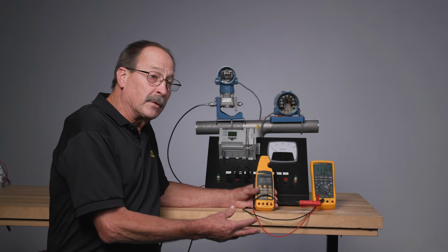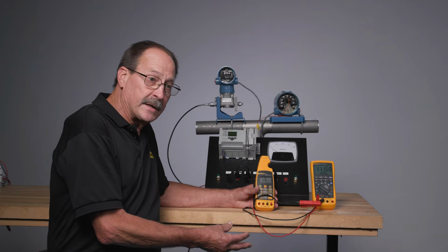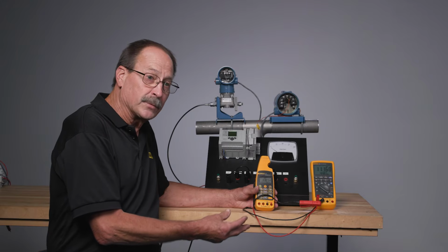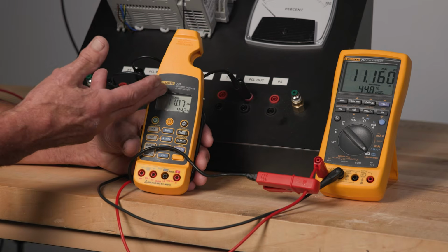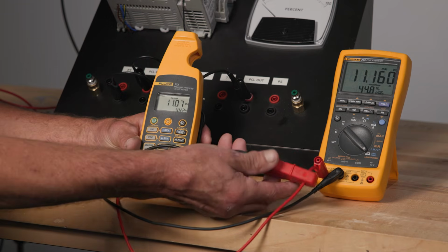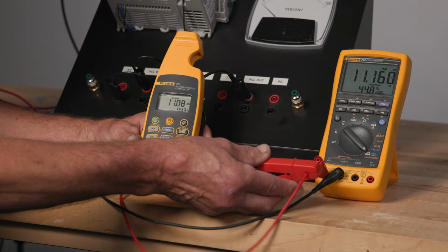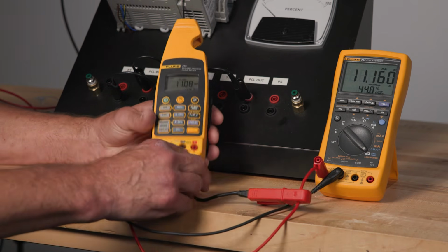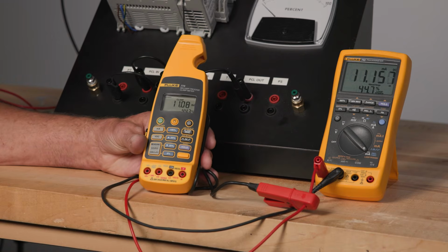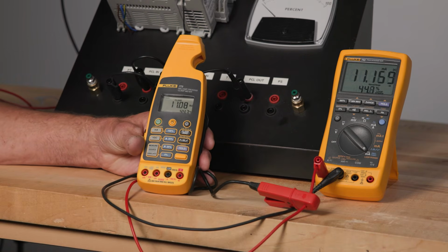This is quite valuable when you have a critical process that can't be shut down, but yet you need to make a 4 to 20 milliamp measurement. The 773 milliamp clamp has the ability to measure the milliamp signals without breaking the loop, but it also has a built-in loop calibrator and voltage signal function.